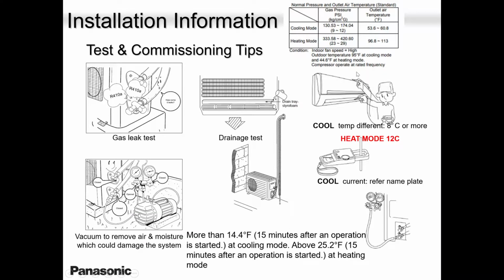Delta T, always see, if you have the time, measure the delta T so that your unit is working well. 14 degrees in cooling and about 25 degrees in heating after half an hour of operation. Okay, after half an hour of operation. 15 minutes is okay, but the longer the better. Make sure you have a good delta T.